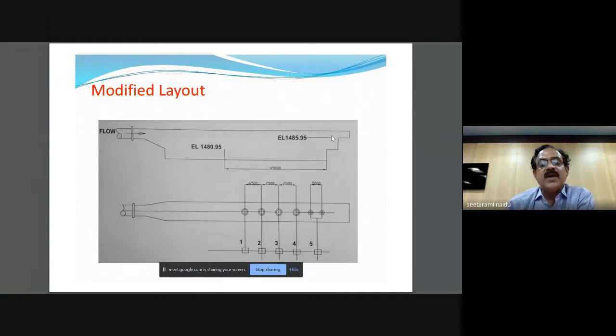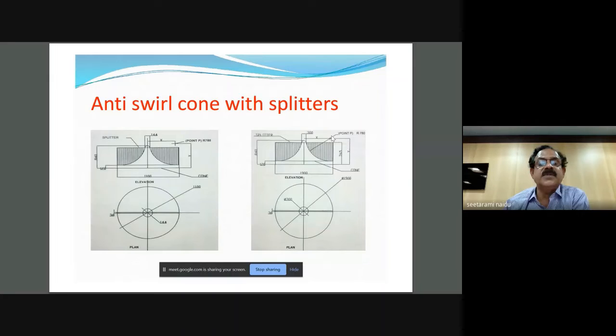Then what was done was that from the flow, the first pump was removed and placed below, and we suggested that in place of 6 pumps, there be only 4 pumps. I mean, a little increased discharge. They accepted. There was a free settling place for this approach, and the spacing was increased. Then we could come to an acceptable limit in the performance of the turbines.